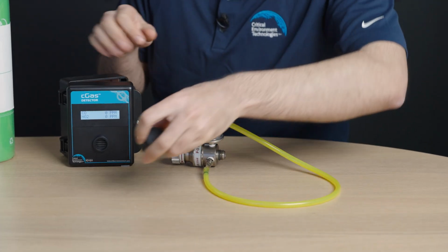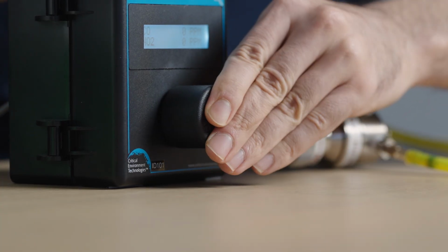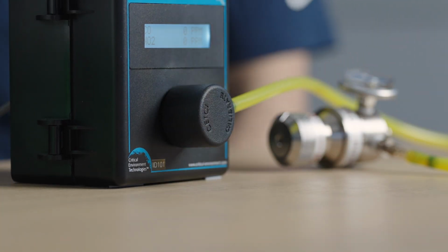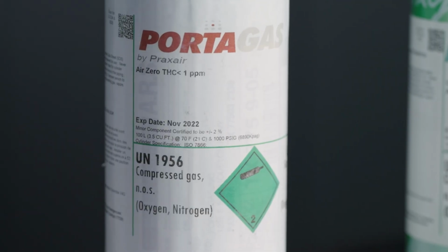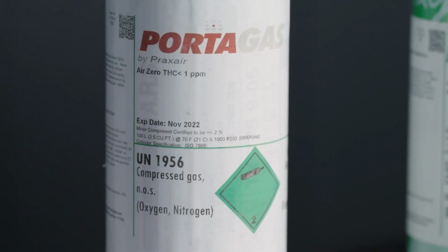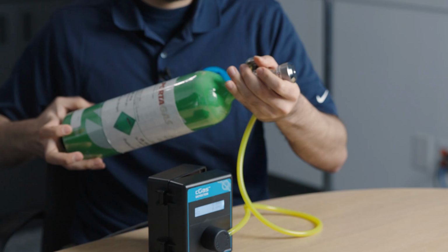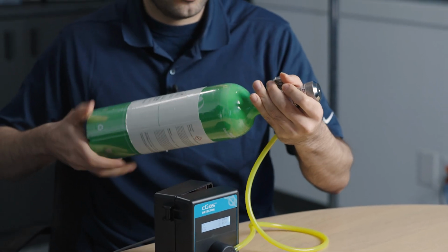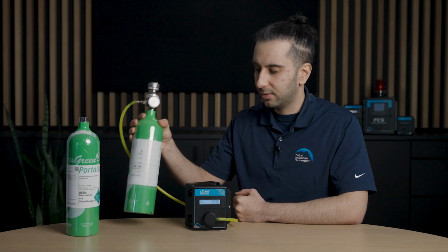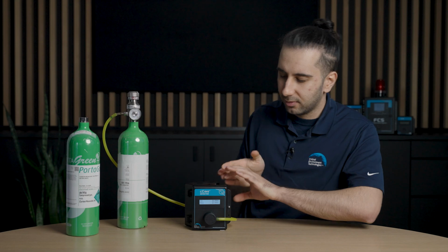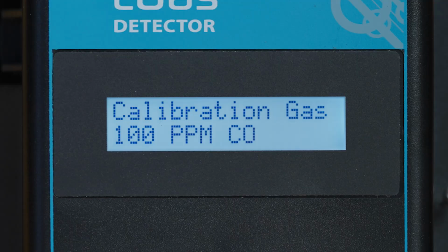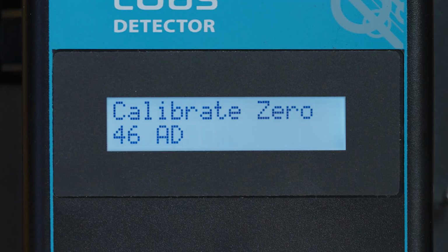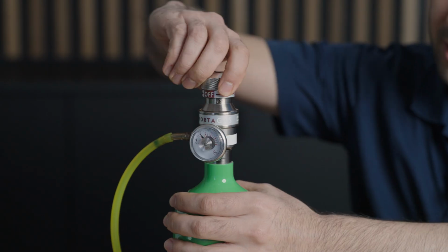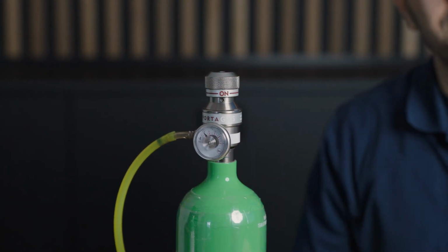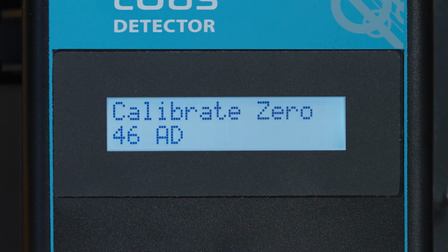Connect the zero gas cylinder to the detector using the tubing and the calibration clip. I am using the air balanced zero gas for this carbon monoxide sensor. Other sensors may require nitrogen balance or other types of gas. Navigate to Calibrate 0 and start flowing the zero gas for a few seconds. Then press Enter to start.